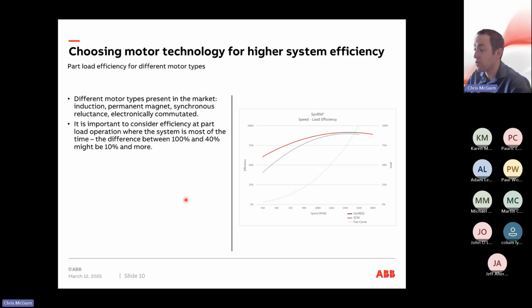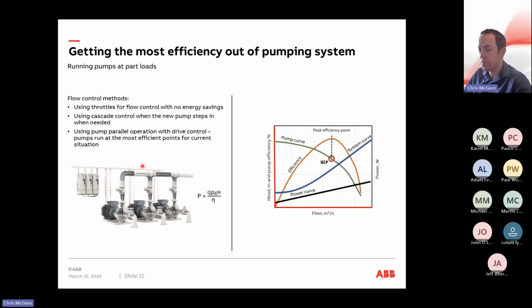What speed your system is actually working at, so you understand what efficiency you're reaching here. Depending on the different types of motor you use, which I'll talk about a little later, you can see differences in efficiency. So this is a standard induction motor against a SynRM, which is our headline high efficiency motor. You can see at lower loads, at lower speeds, there's a drop off in the efficiency levels of the induction motor, whereas in a more highly efficient motor, it doesn't drop off quite as much. So you're able to get those savings by using a better level of motor equipment.